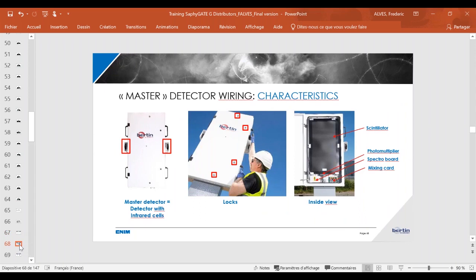Have a look first at the master detector. As we said before, you can easily identify the master detector thanks to its two infrared cells on each side of the housing. You also have to identify the locks on the master detector. You have 4 locks on the door, so use the key to open the door. You have a picture of the inside view, only as a reminder of what we have seen. You have the scintillator, and you also have the spectral board and the mixing card.